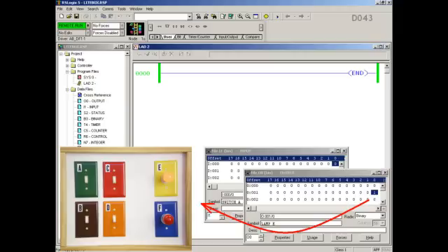And if we try to look at that sequence in the RSLogix software, once again, we find that the transfer of information from the bit to the output device takes place so fast that we can't see the step-by-step action at all. It's so fast that it looks like it's instantaneous, but now we know that's a misconception. Actually, the transfer takes place only once per scan cycle, precisely on step number 3.